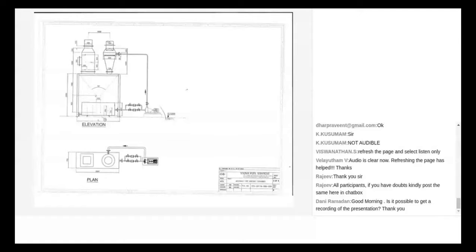So you've seen the simple engineering of a package boiler, which looks crude and primary—where you put wood, coal, or briquette on a stationary grate and give air from the bottom. There's an ID fan which handles gases at about 250 degrees centigrade. That's the simplest setup. It consumes around 60 to 70 lakh rupees per year in any small industry, and therefore it's a great opportunity for budding entrepreneurs, engineers, or consultants to educate them and also improve the environment.